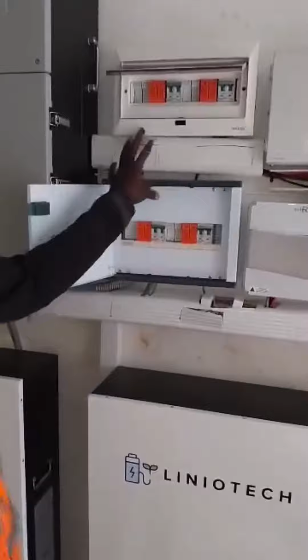From there we have our combiner boxes. We have two combiner boxes, and each combiner box has two PV strings. In each combiner box we have a DC fuse, DC surge protected device, and DC breaker. That's what the other string also has.